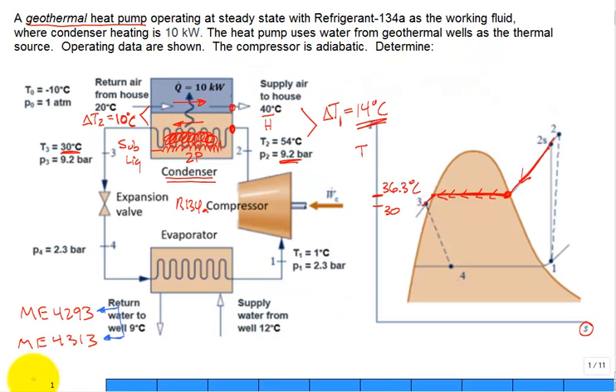It's more challenging for the refrigerant because of the phase change, but we already know what the shape looks like from the TS diagram: it comes down, then it's flat for a long way, then comes down again. So from 54 degrees, it comes down to about 36.3 degrees C where it hits saturation, stays flat through the two-phase region, and then exits at 30 degrees C.